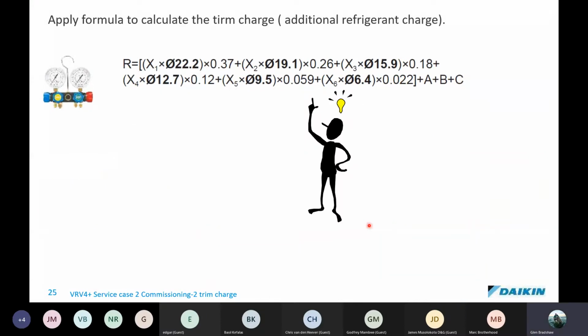All right, so now that you understand how that is done, the most important thing that is required from you guys when you're installing is that you know the amount of liquid line lengths per diameter of piping that you've got. Without that, we cannot even begin the calculation. So that is critical. So it's very important.